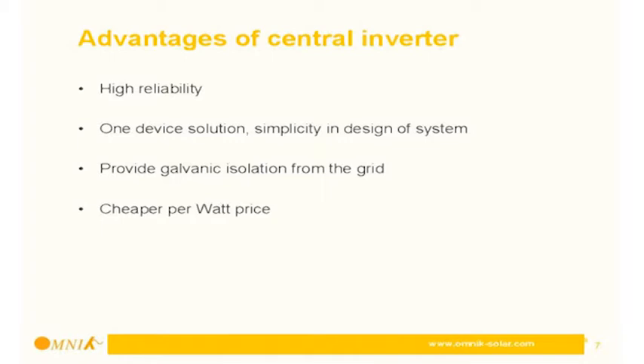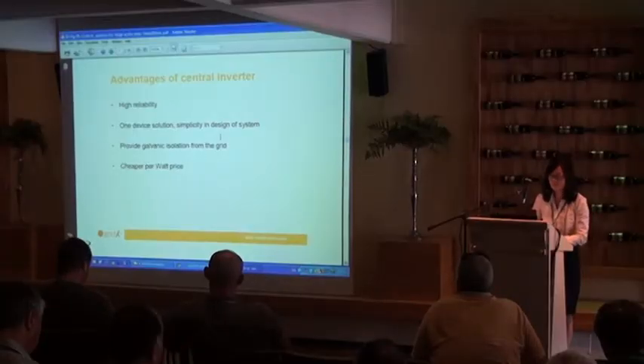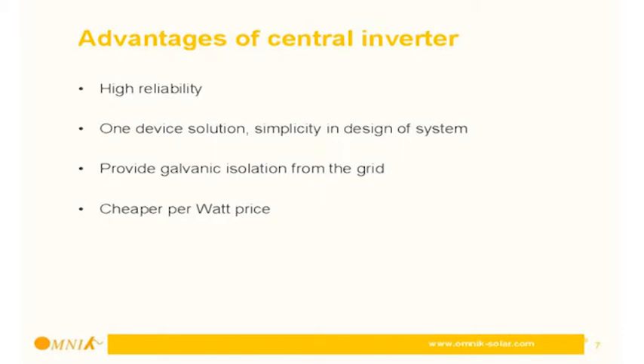So in total, the advantages of the central inverter mostly rely on high reliability, and there is just one device for the whole system. It is a very easy solution, very easy to design, and in total a cheaper price per watt, which is also the largest advantage of the central inverter. As we talk about the string inverter, in contrast, the string inverter concept uses multiple inverters for multiple strings of modules, like the Omnik 20K, which we have been applying in multi-megawatt applications.